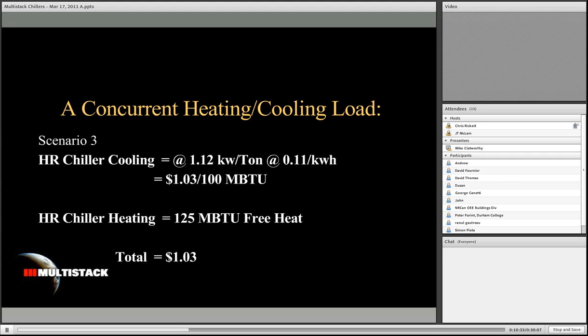So let's move on to scenario three. And as you might have guessed, scenario three is a dedicated heat recovery chiller applied as we illustrated in the diagram previously. So a heat recovery chiller operating at 1.12 kW per ton and 11 cents per kilowatt hour. So my pure cooling efficiency in this example has to be elevated. I'm making hot water with this chiller, so my pure cooling efficiency is actually deteriorated. But that's okay because the hot water has become free. So my therm of concurrent heating and cooling now costs $1.03.